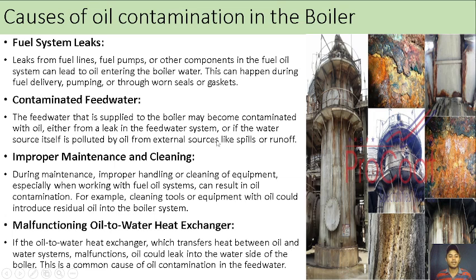Improper maintenance and cleaning. During maintenance, improper handling or cleaning of equipment, especially when working with fuel oil systems, can result in oil contamination. For example, cleaning tools or equipment with oil could introduce residual oil into the boiler system. Next, we have the malfunctioning oil to water heat exchanger. If the oil water heat exchanger, which transfers heat between oil and water systems, malfunctions, oil could leak into the water side of the boiler. This is a common cause of oil contamination in the feed water.